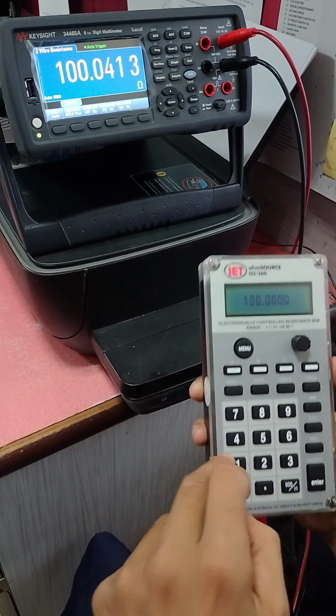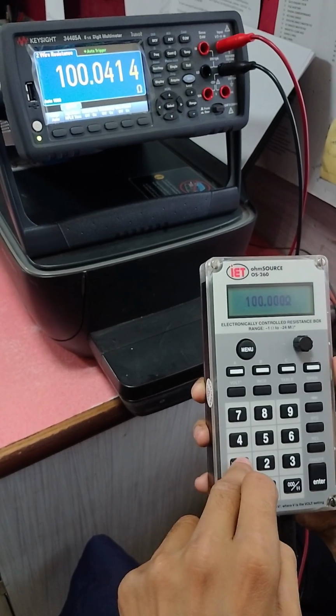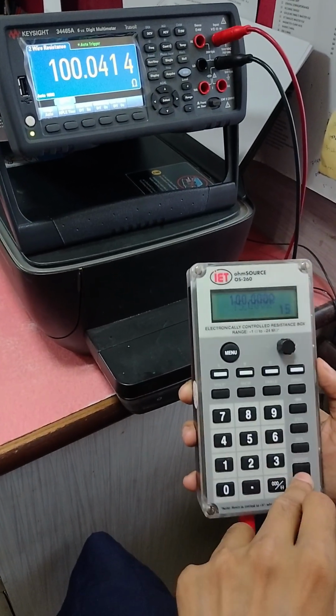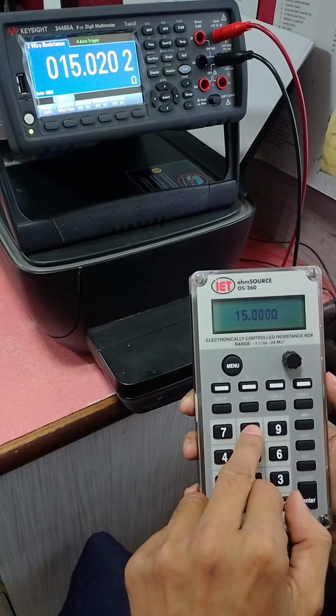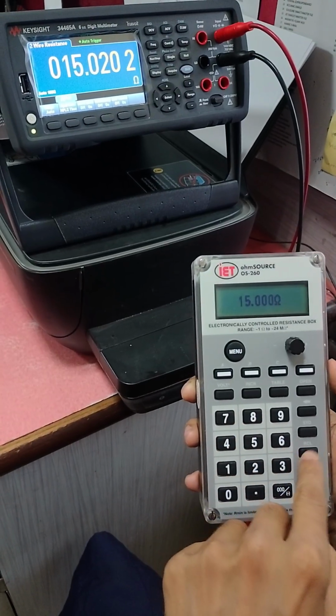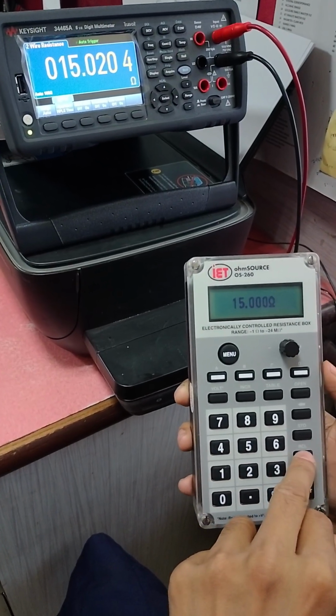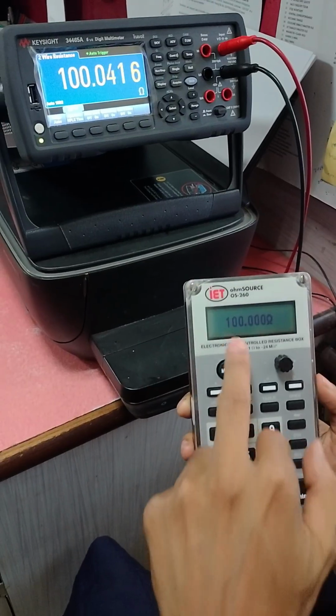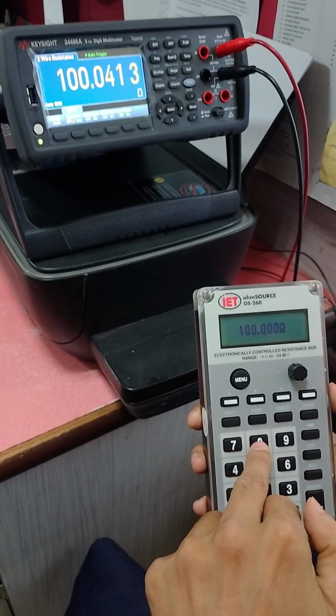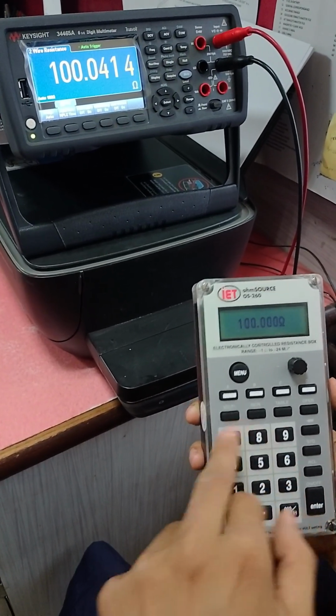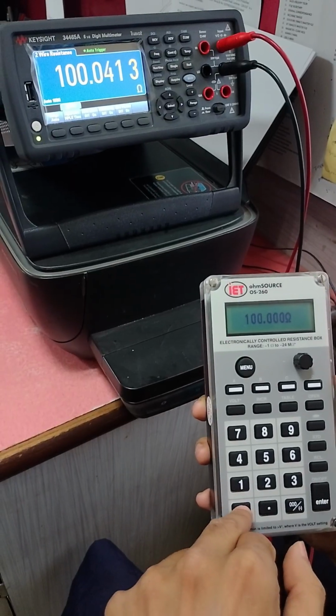To verify it, just go back and press any other value, 15, so it is showing 15. Now to get the value at 8, you just need to use the recall button. Press recall and press 8. You can see 100 ohm is set at this 8. Similarly you can set any value on any of these buttons.